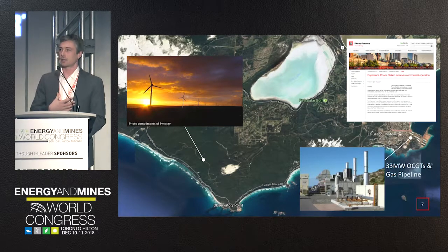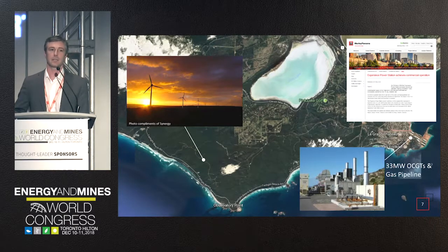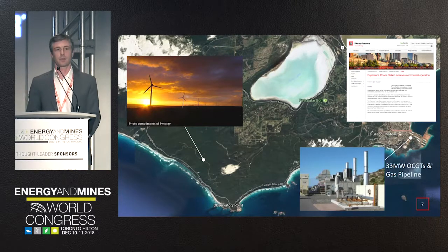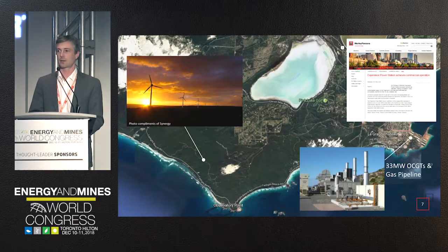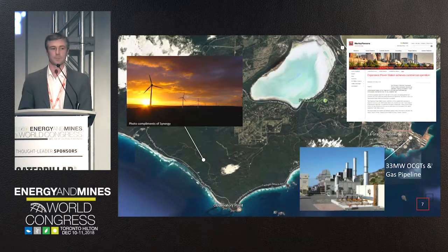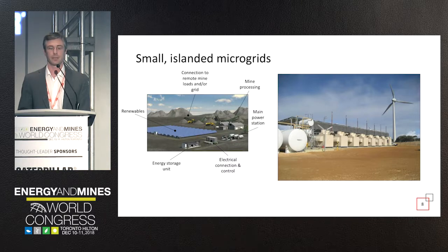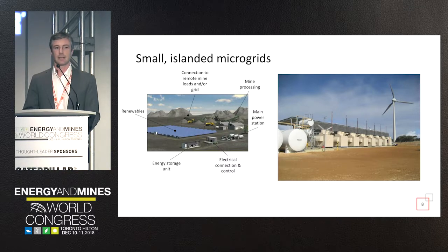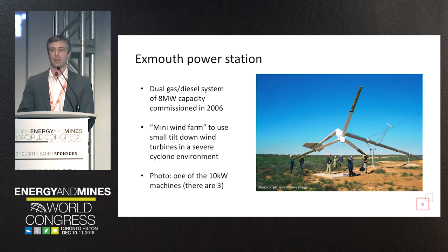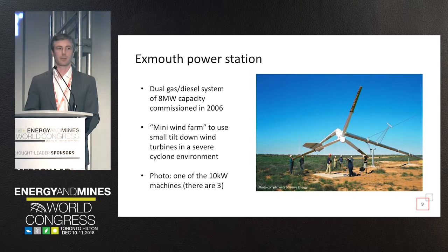What our modeling showed was that using a measure of natural gas and two wind farms was able to achieve the lowest levelized cost of energy. Looking out to 2050, I don't expect to see a lot of hundred percent renewable mines except in areas where the renewable resource is very attractive — parts of Africa, Latin America, some parts of Australia. What we've seen more with small and islanded microgrids is the value in hybrid systems: reducing diesel to the point where you're getting your lowest levelized cost of energy while ensuring reliable operations.